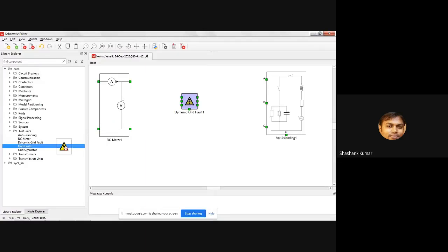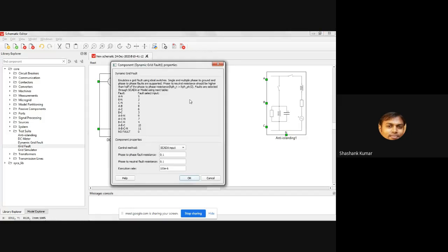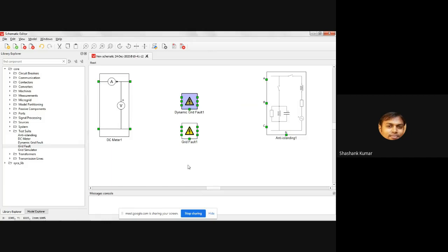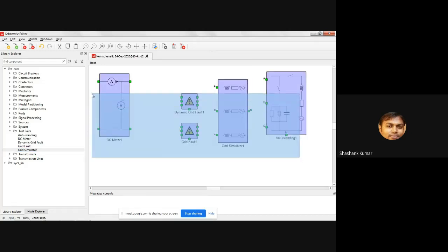Here two faults are available - this is the grid fault, and another is the dynamic grid fault. What's the difference? Both are same in fundamental concept, but the difference is you can change the fault scenario in this dynamic fault from SCADA by changing these numbers. According to the fault you want to create, just select the number, and you can create that fault while your simulation is running. Next is the grid simulator you get with this one. These are available in the test suite library.